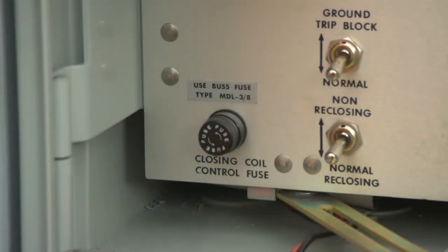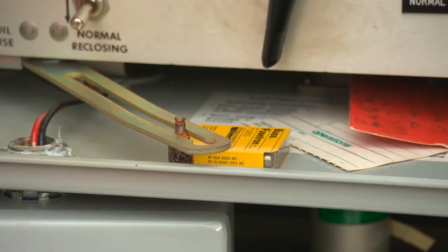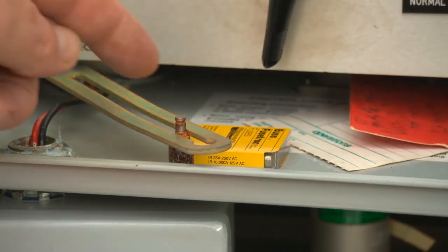If you find yourself in the situation where the close handle within the control does not function and the manual operating handle for the recloser is in the up position, you need to check the condition of the slow-blowing closing coil fuse. Typically, there are spare fuses in the bottom of the enclosure.